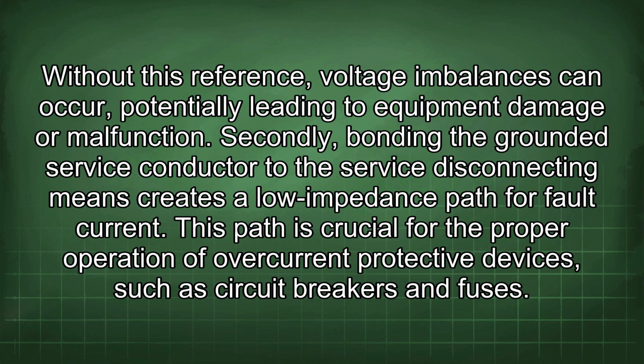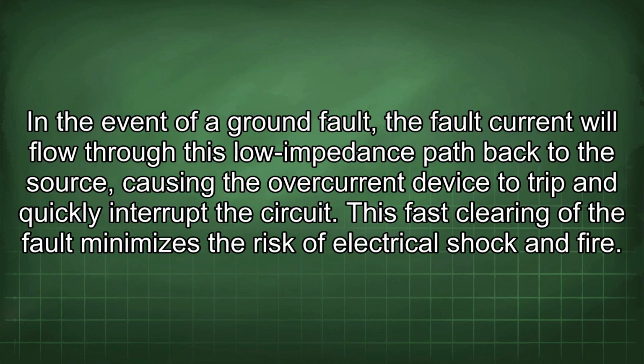Secondly, bonding the grounded service conductor to the service disconnecting means creates a low impedance path for fault current. This path is crucial for the proper operation of overcurrent protective devices, such as circuit breakers and fuses. In the event of a ground fault, the fault current will flow through this lower impedance path back to the source, causing the overcurrent device to trip and quickly interrupt the circuit. This fast clearing of the fault minimizes the risk of electrical shock and fire.